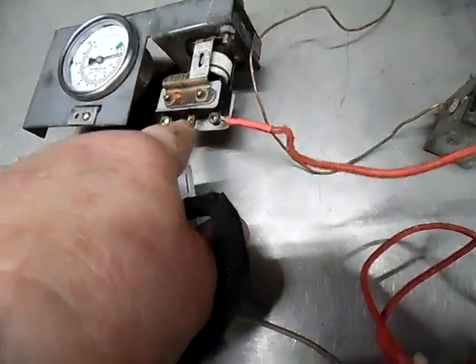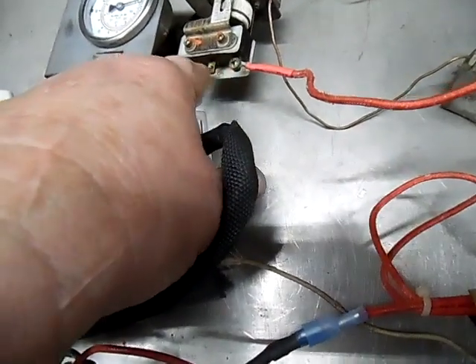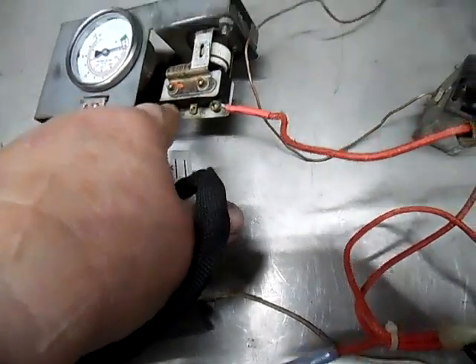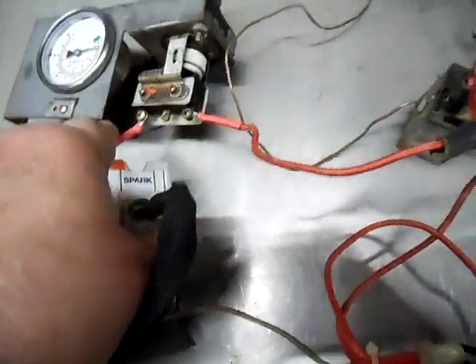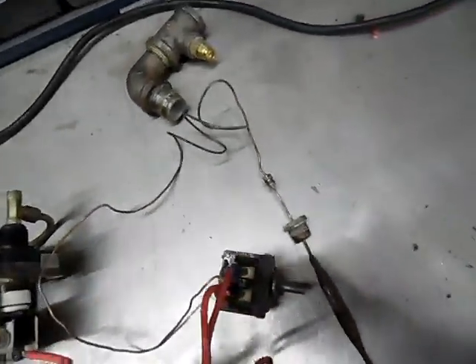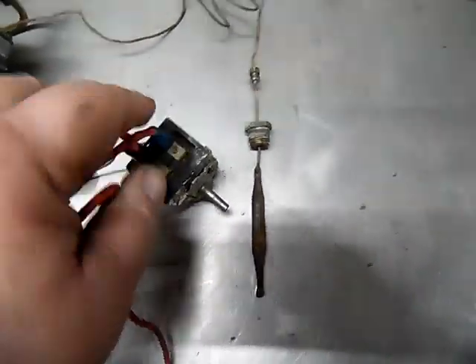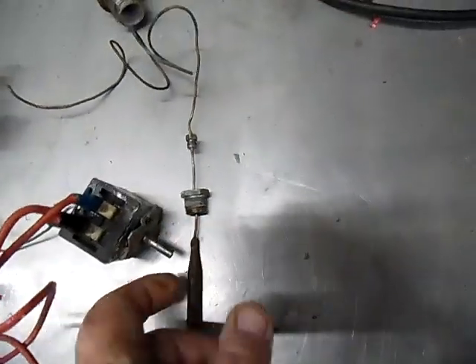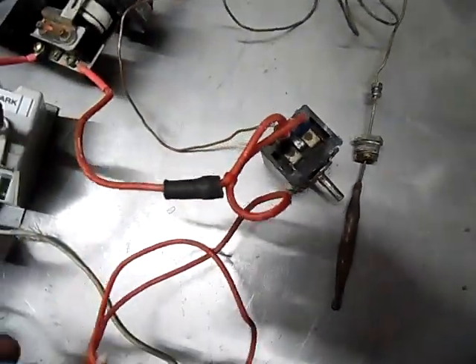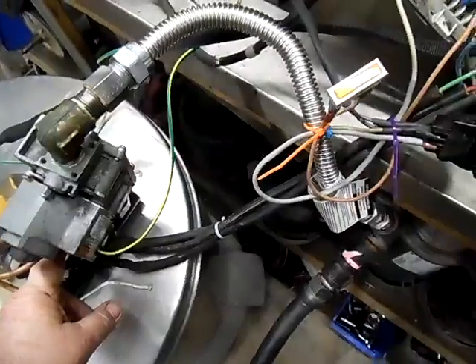It's kind of like a light switch. It's always on, meaning it always has continuity. These two wires are switches on. So the power will go through here, then it goes to your thermostat. If you have your thermostat turned all the way up and your thermostat is operating correctly, then it will get back and it'll start heading to the wire all the way to the valve.